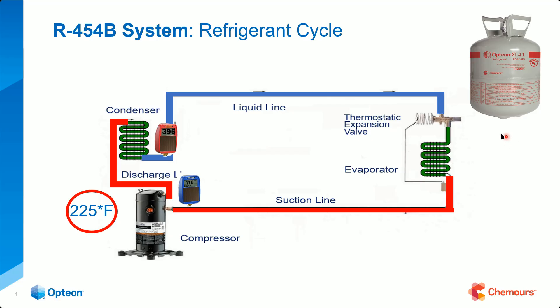When we drop pressure, we drop temperature — there's a pressure-temperature relationship. So this is a TXV, but quite honestly it's a pressure dropper. That's what we're trying to do: drop the pressure because when we drop the pressure, we drop the temperature. When we drop the pressure and drop the temperature, we're changing state from liquid to saturation — about 75% liquid, 50% liquid, 25% liquid. The goal is to be all vapor, superheated vapor, by the end, so we don't hear crunchy noises in our compressor.